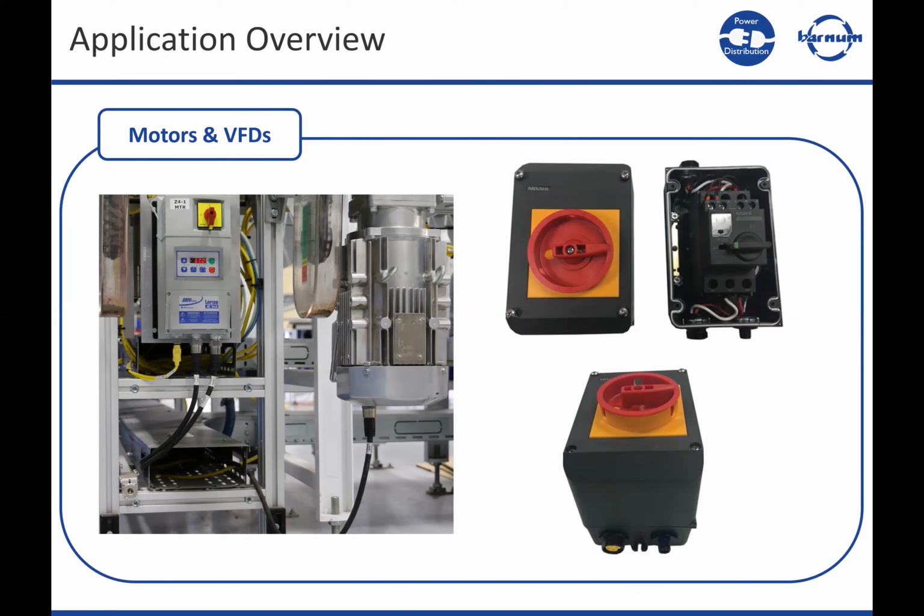We've got a variable frequency drive that allows us to put power connections in the field, and we could bring power in and power to our motor. Not only that, but we're able to bring network communication to the same unit too. So whether it be Ethernet or Profinet or even IO-Link, we can pass that to this device. So out of your main cabinet, you're essentially running one communication cable and one power cable all the way along the conveyor.